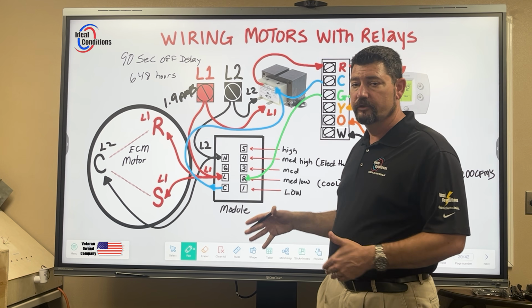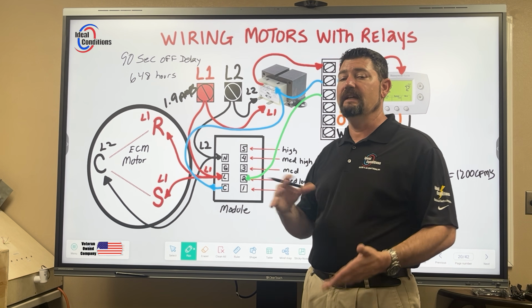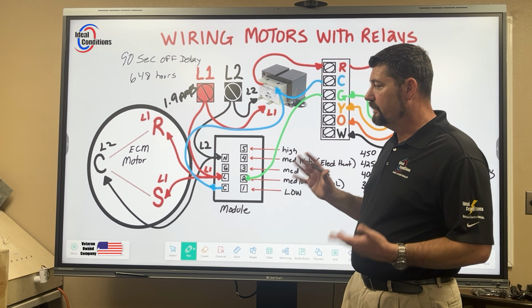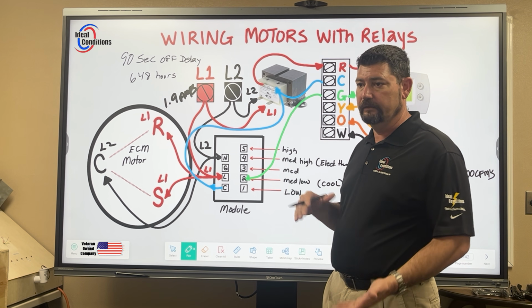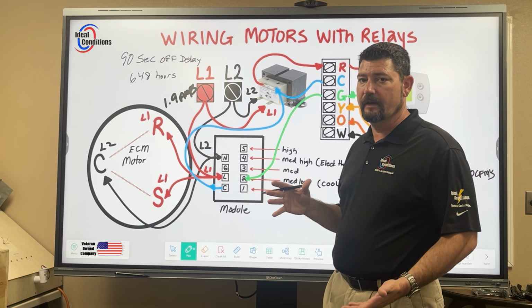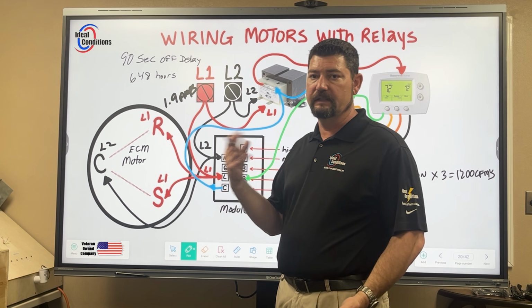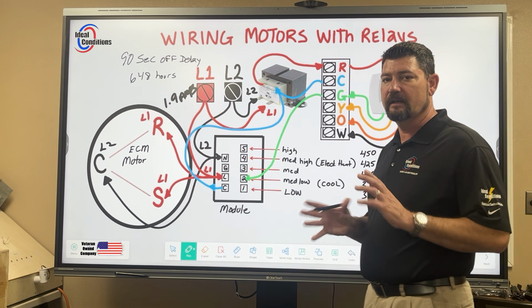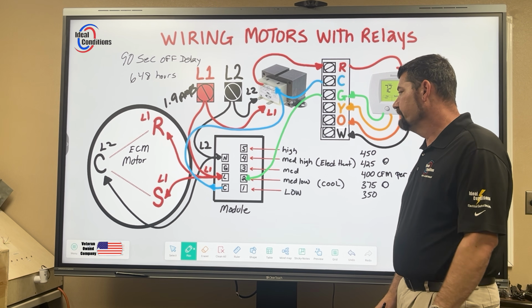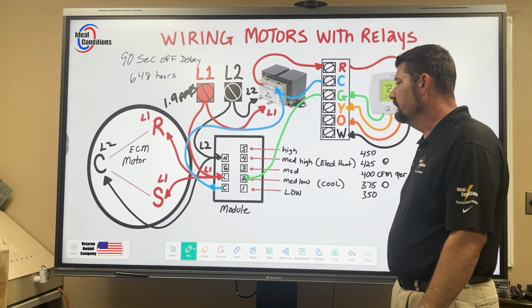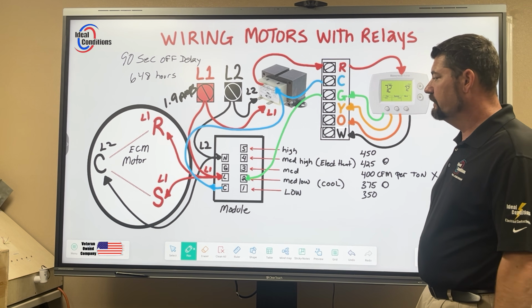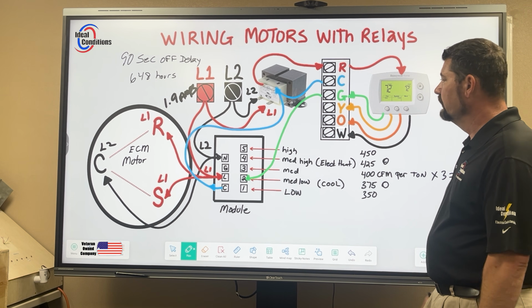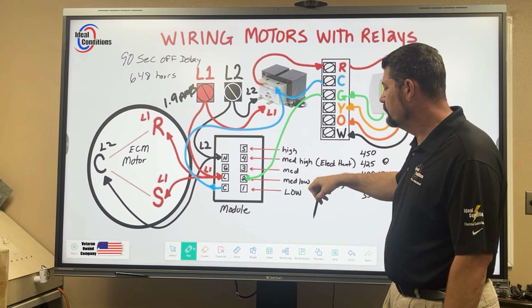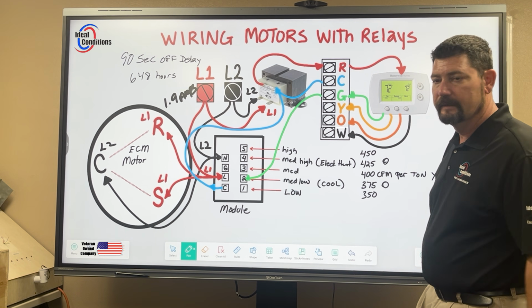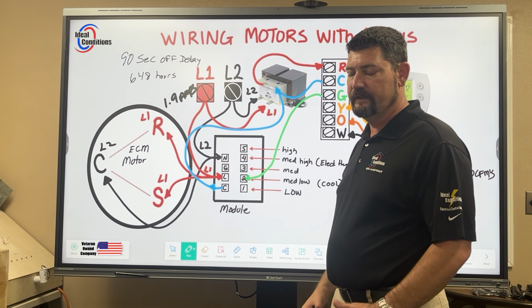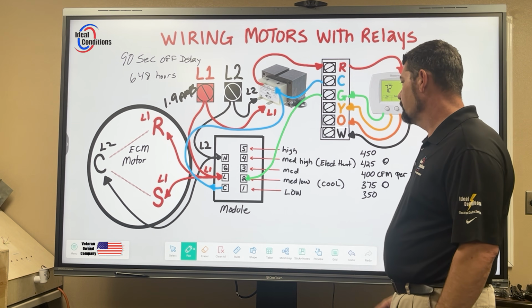That ECM just gave you 2 speeds that it can run that a PSC can't, right? If I try to run the PSC motor with 2 speeds, like low and medium, I'm going to have a problem. It's not going to work out very well. I have to be able to drop 1 speed out to continue another speed. It can be done, but it's going to take a couple of relays to do that. And that's really all there is to it. No light bulbs to wire up here. Could you integrate it? Yeah. Simple. When I get a 24-volt call, I can have that go to a relay, and building automation can now be implemented where I can have something else happen. You just have to put relays in. Long story short, that's pretty much it.